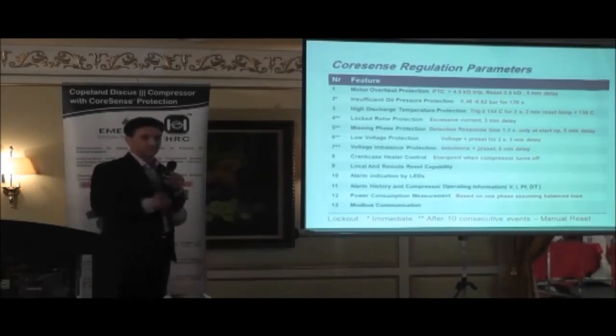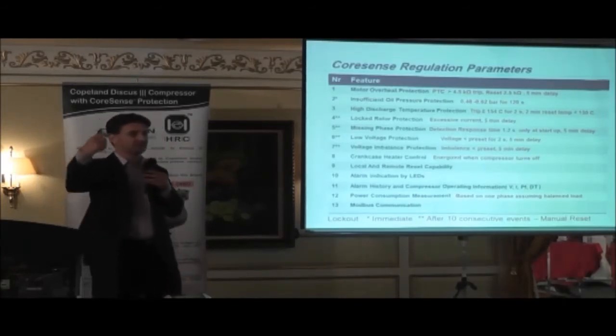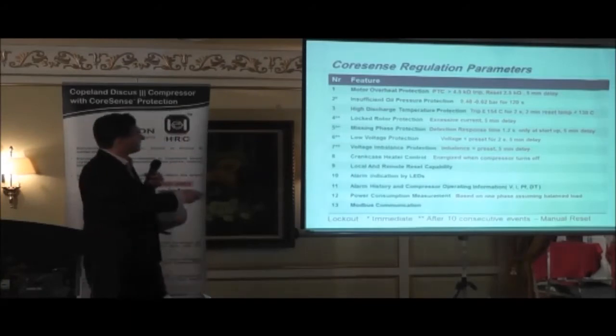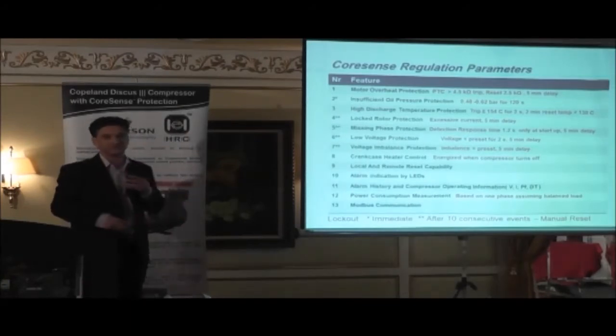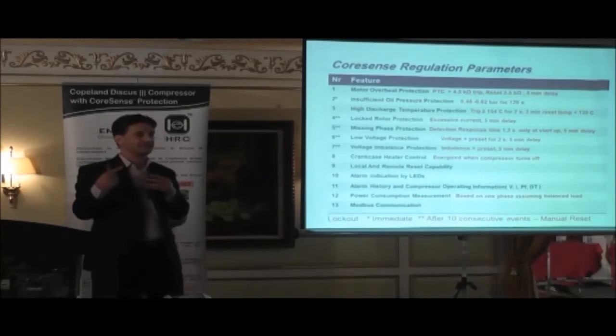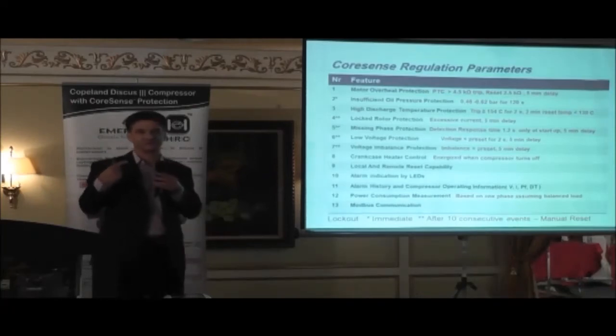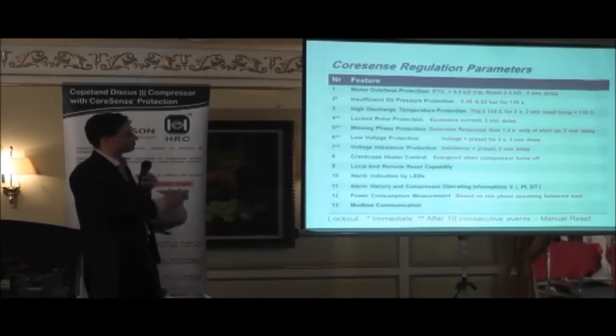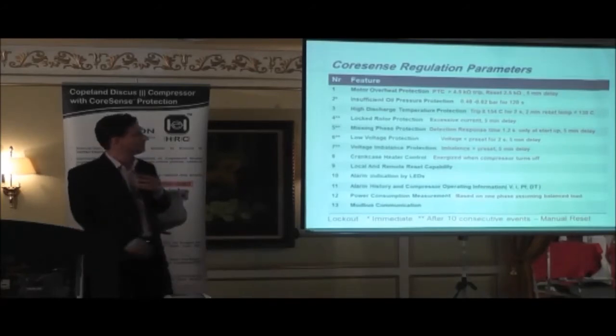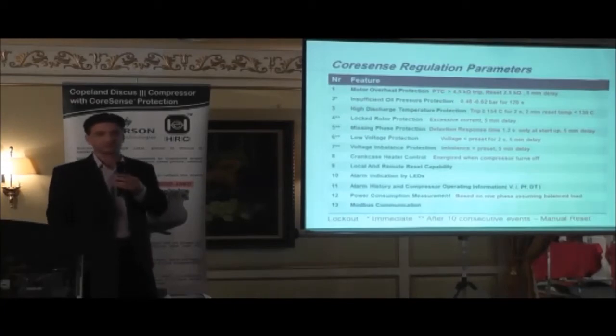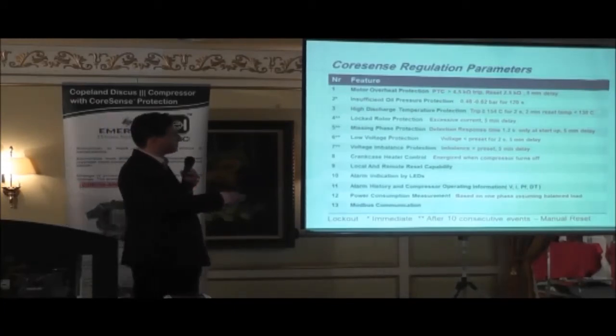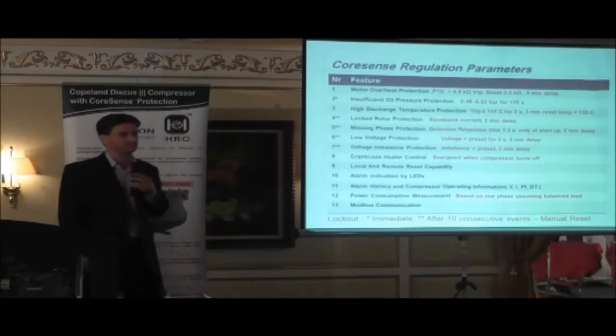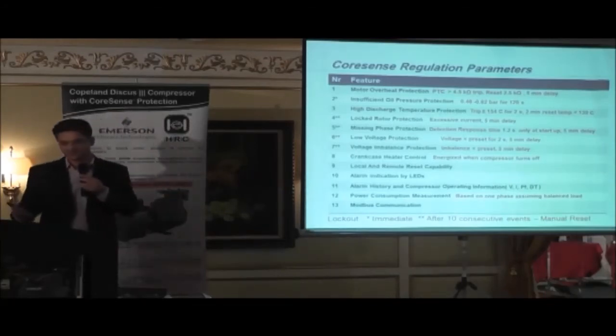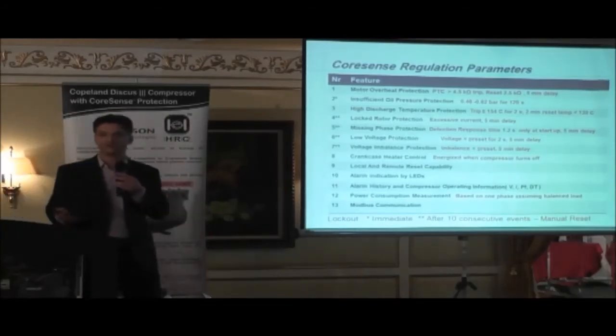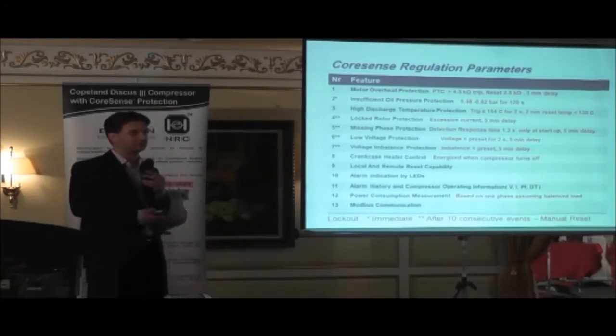Item number 3. This is the probe that's connected into the cylinder head. This probe is set at 154 degrees. If the cylinder head temperature exceeds 154 degrees for 2 seconds, it will switch off the compressor. And it's got a 2-minute delay before it resets. It will also only reset if the temperature is below 130 degrees C. Alright? So this is a protection feature to prevent the compressor from overheating, which was not offered before.